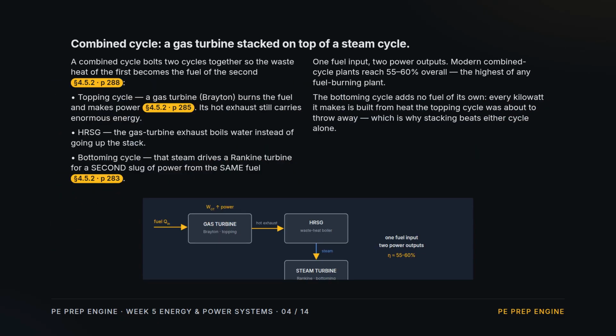A combined cycle bolts two cycles together, so the leftovers of the first feed the second. On top sits a gas turbine, a Brayton cycle, burning the fuel and making power. Its exhaust is brutally hot and would normally go straight up the stack. Instead, it pours into a heat recovery steam generator, an HRSG, which boils water. That steam drives a Rankine steam turbine for a second helping of power from the same fuel. One fuel in, two power outputs out. Modern combined cycle plants reach 55 to 60%, the best of any plant that burns fuel. The bottoming cycle adds no fuel of its own. It lives entirely on heat the gas turbine was about to waste.